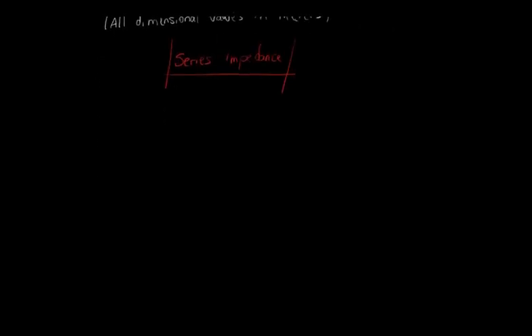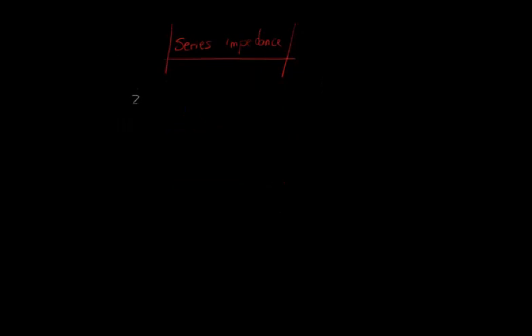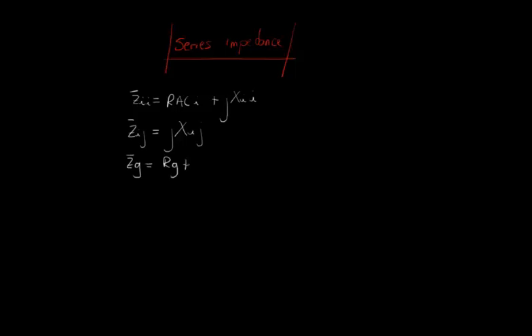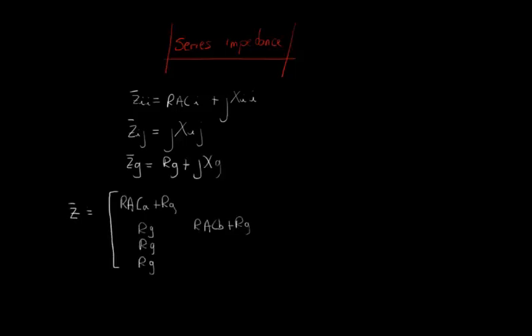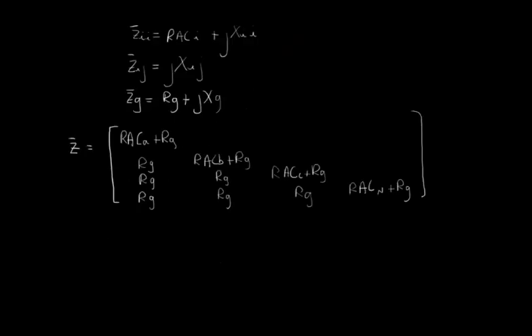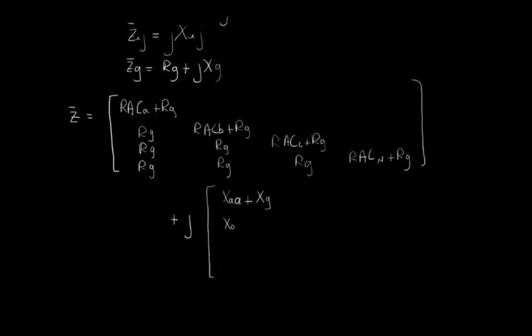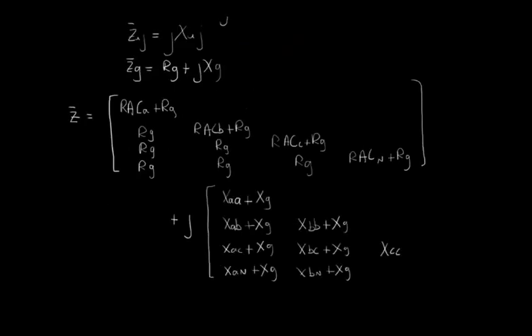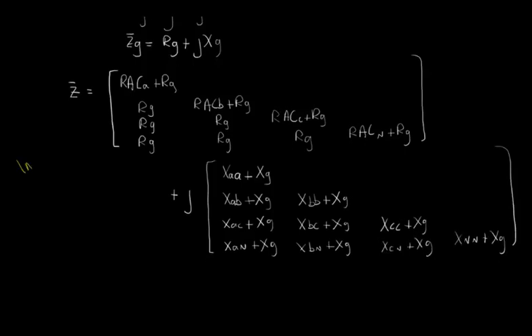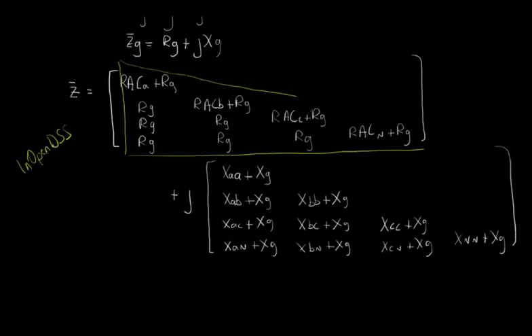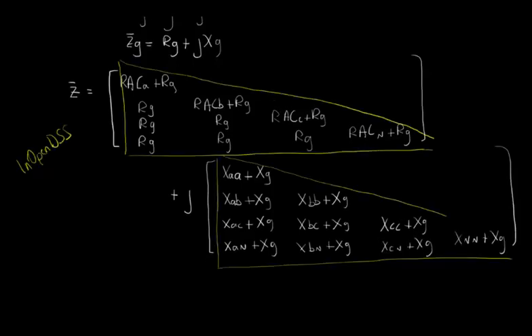Now, we can split this matrix into real and imaginary parts and put them together. By doing so, we end up with a symmetrical resistance matrix and a symmetrical reactance matrix, which can be directly used in OpenDSS to define the line element through the lower triangle, as we did in line element tutorial video.